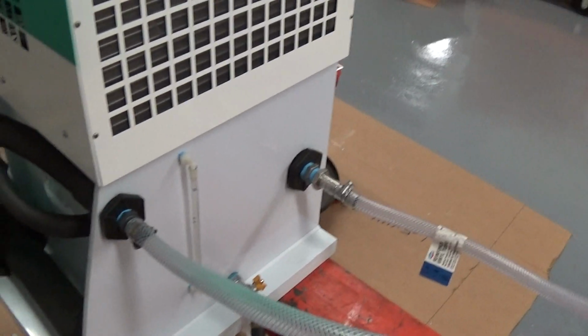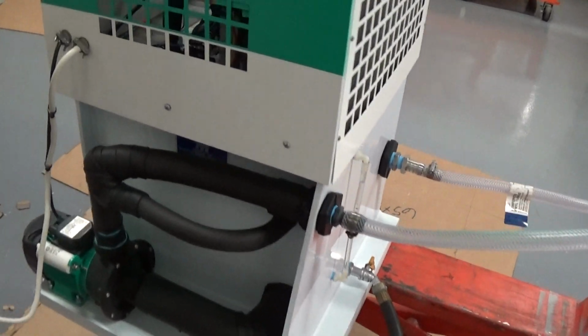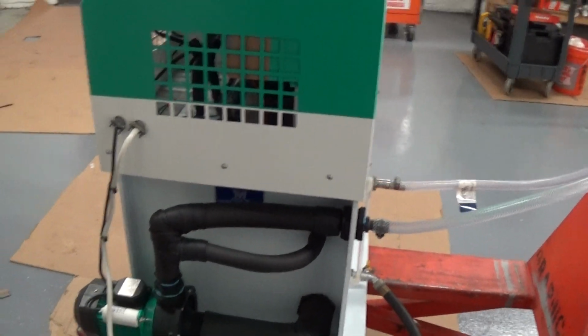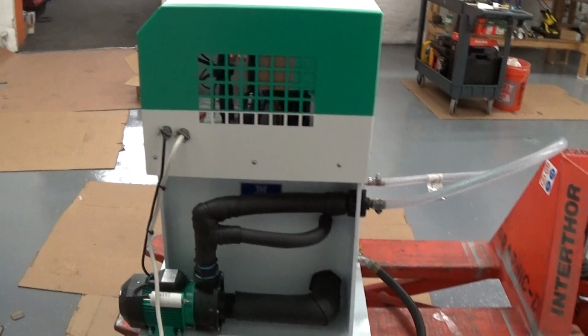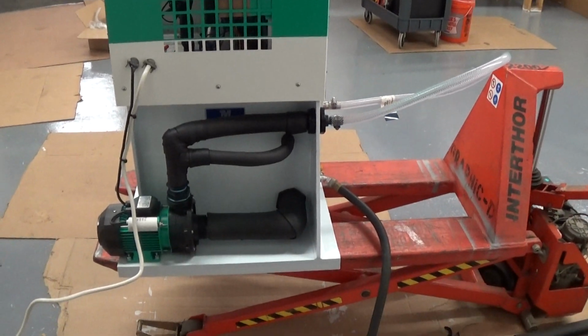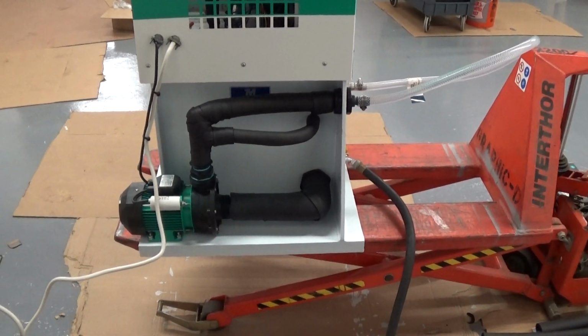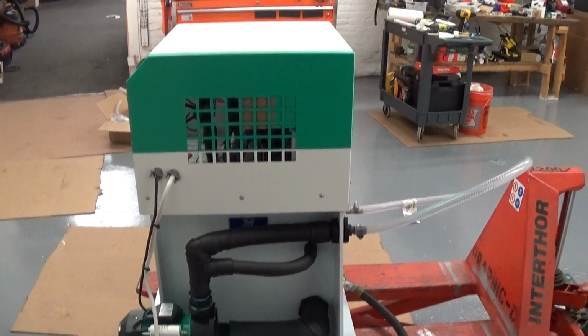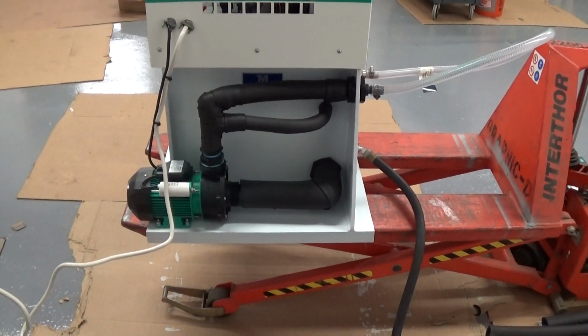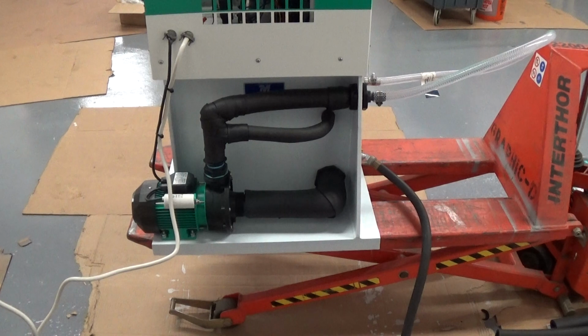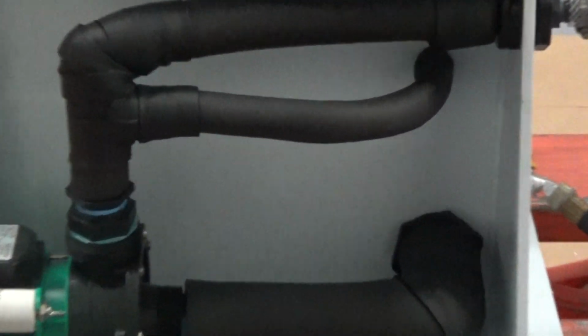Anytime you run less than 48 degrees Fahrenheit, you should run a glycol solution. In fact, it's nice to run at least 10 or 20% even on temperatures above that for rust inhibitors, for any metallic components that might be in your process loop. This line you see here, that's our fixed internal bypass.